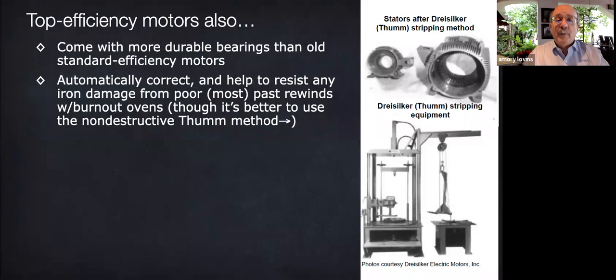And that iron damage is caused by poor rewind practice using the standard so-called stator burnout ovens rather than the Thumm method shown on the right and used by the US Navy, where you very gently warm the stator and then persistently gently pull the windings out of the slots with a hydraulic puller. So you end up with a perfectly clean set of laminations ready to rewind the wire into the slots, just as good as new. So just the avoided iron loss plus resizing typically about doubles the savings compared with what you would expect just from rated efficiency. I'm talking here about energy savings.